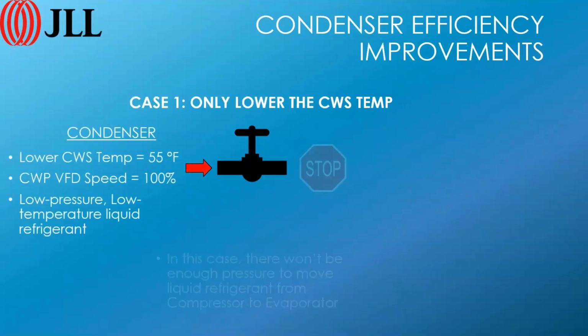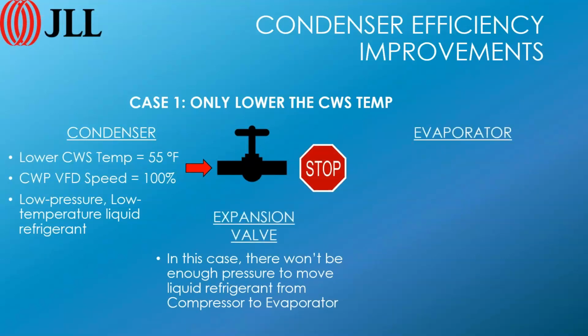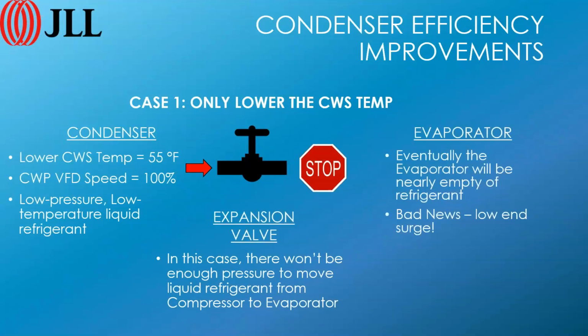Now, if we just drop the temperature down only, what you'd end up with is not enough pressure inside the condenser to push refrigerant out, and eventually the evaporator would empty out of refrigerant. Pressure would drop lower and lower, and as that pressure drops, the pressure difference across the compressor bundle gets higher and higher, and you'll run into low end surge.